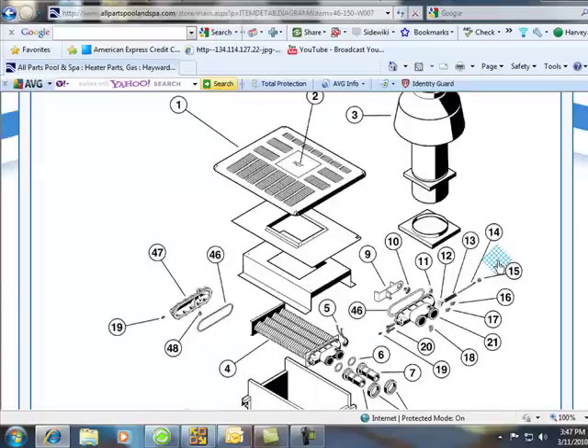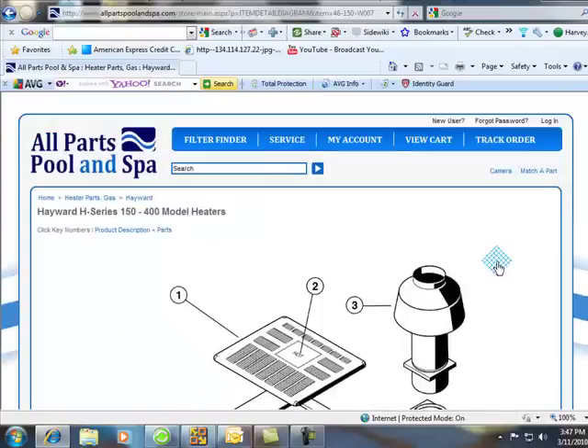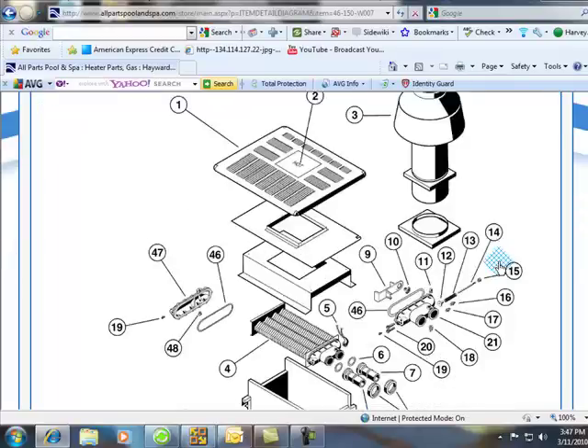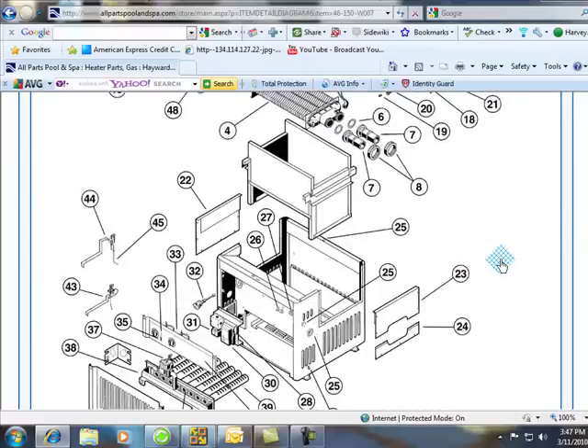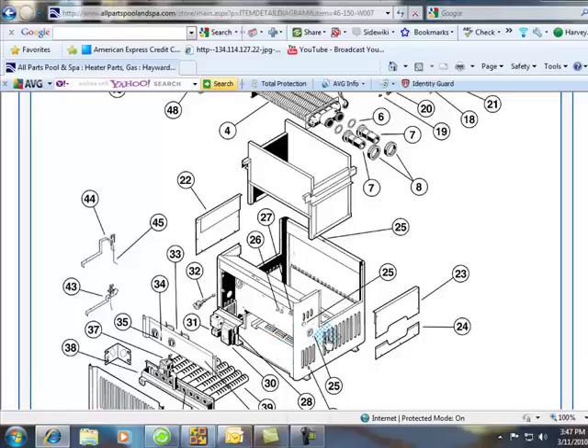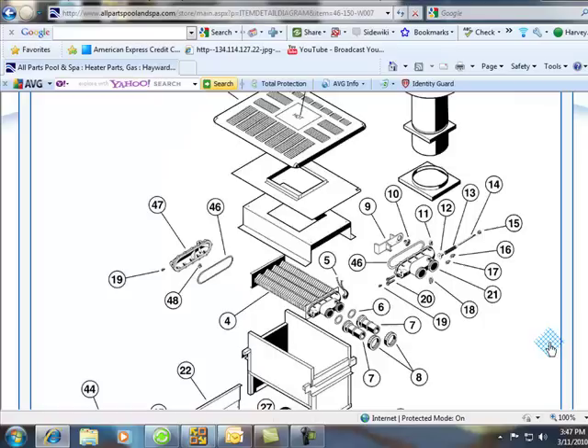Now, I'm doing Hayward. As far as a millivolt heater, Jandy, whoever, Pentair, they're all basically the same. You got a generator for this pilot system. If it's on, and the gas valve is on, you got a safety loop. Ohm it out. Just ohm it out. Start with the basics on a millivolt.